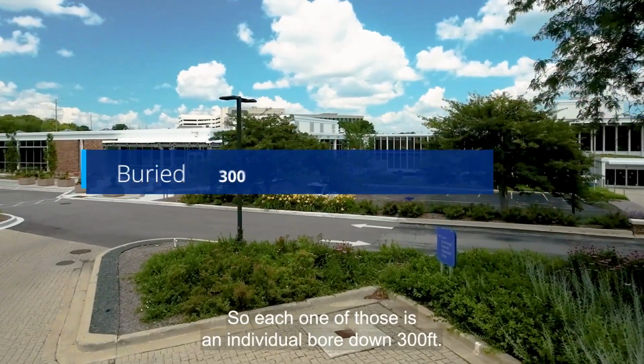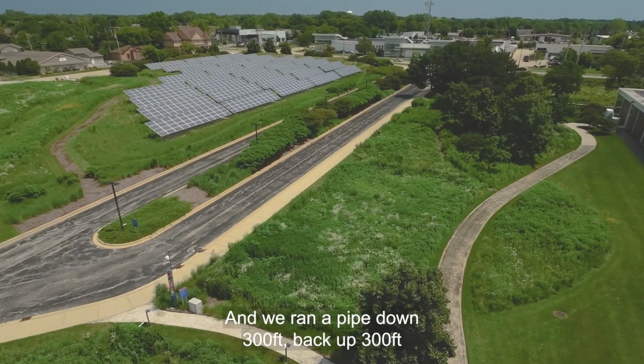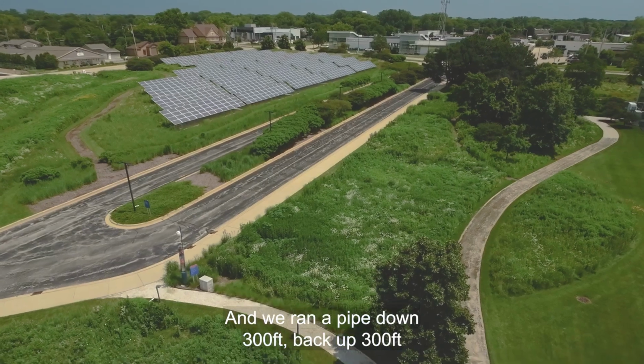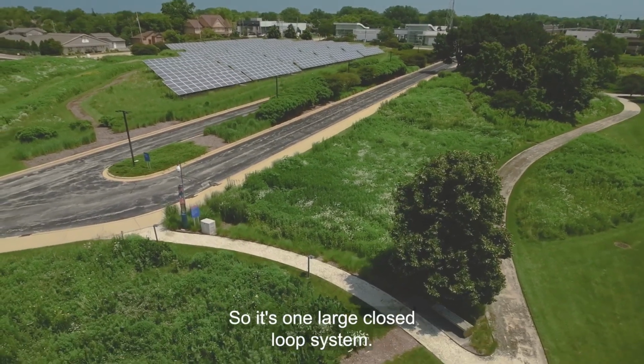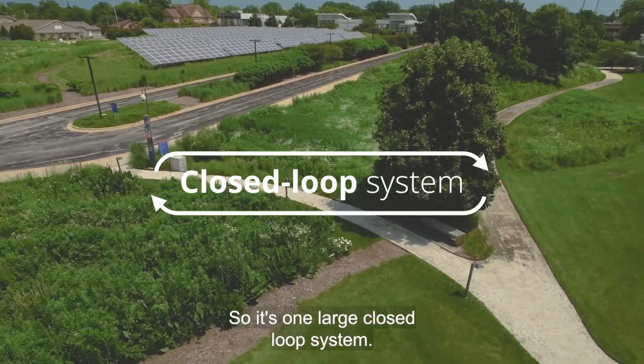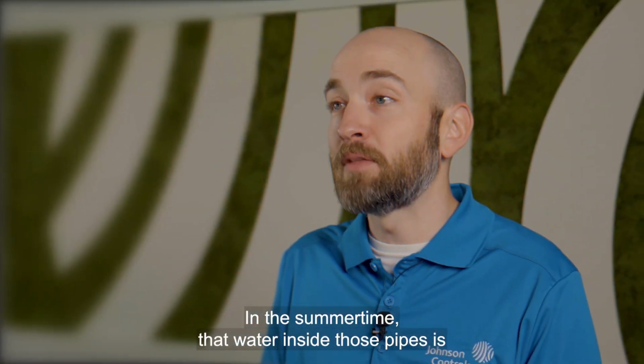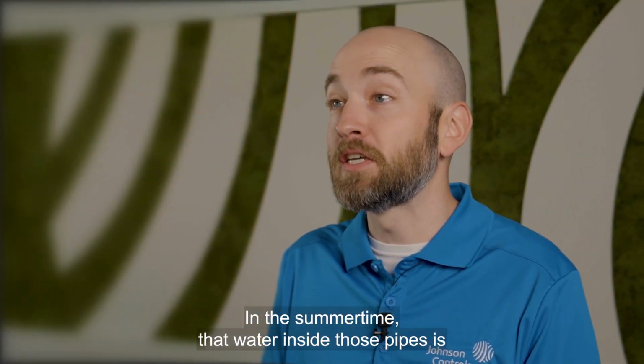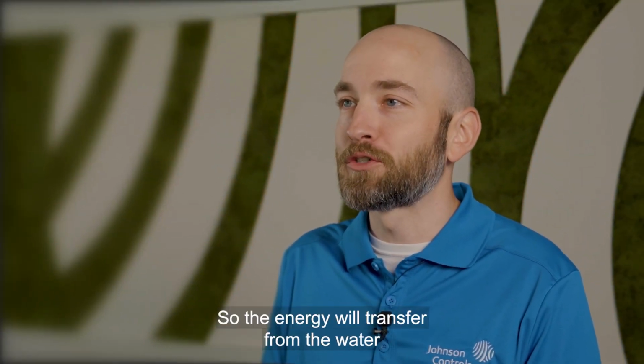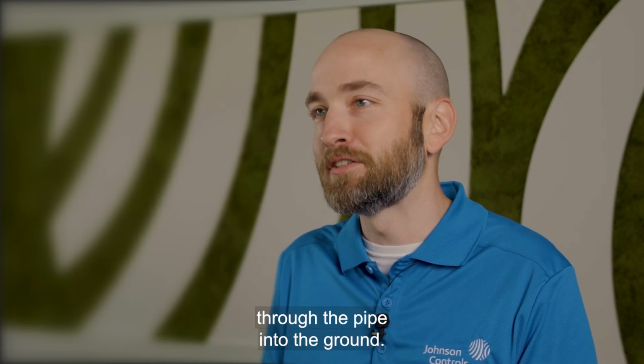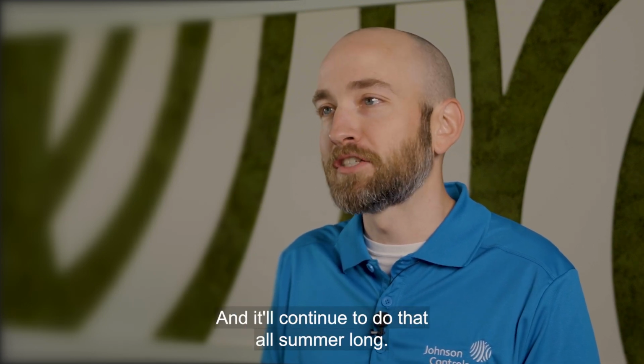So each one of those is an individual bore down 300 feet, and we ran a pipe down 300 feet, back up 300 feet, and connected them all together. So it's one large closed loop system. In the summertime, that water inside those pipes is warmer than the ground, so the energy will transfer from the water through the pipe into the ground, and it'll continue to do that all summer long.